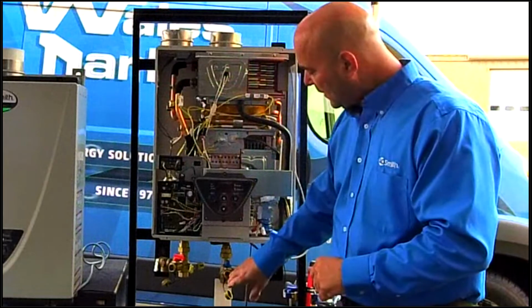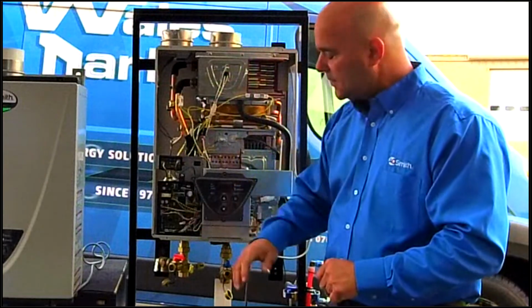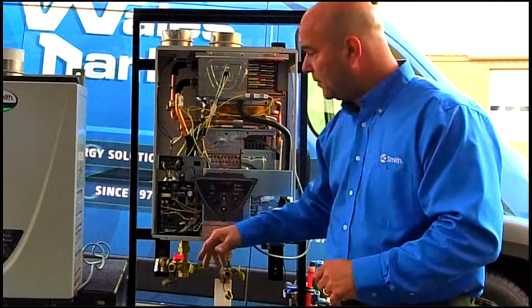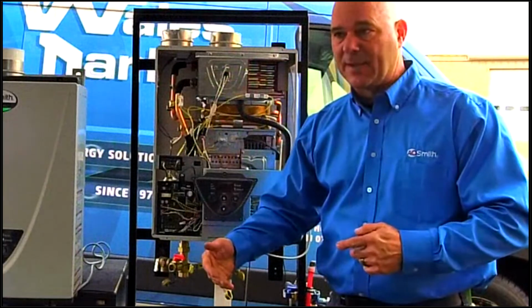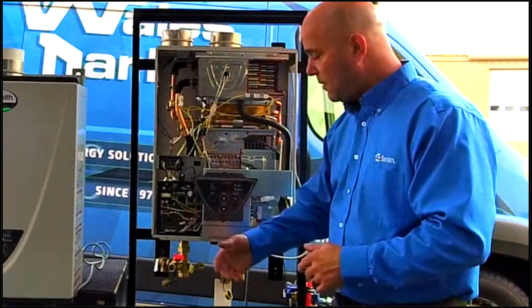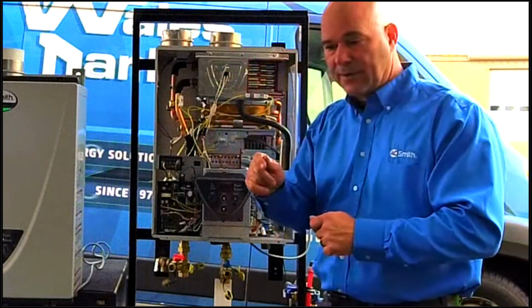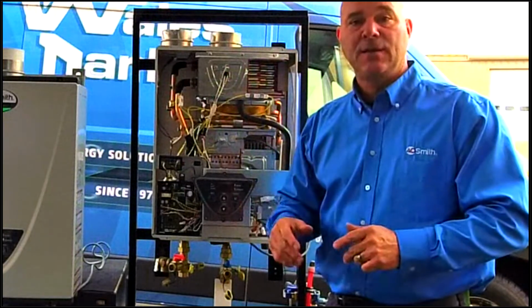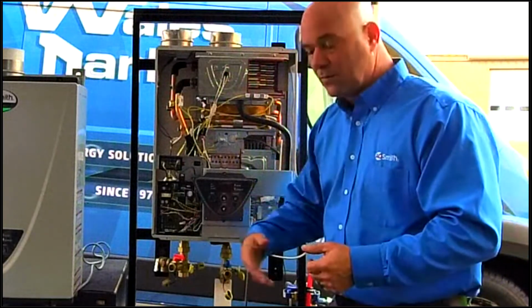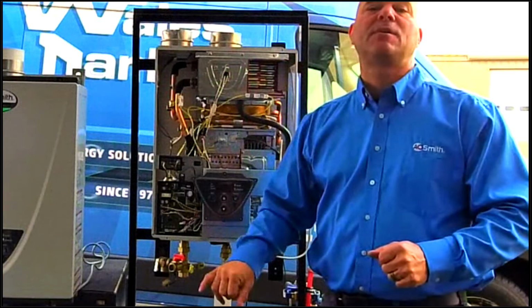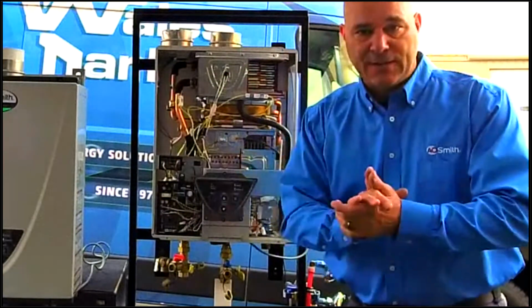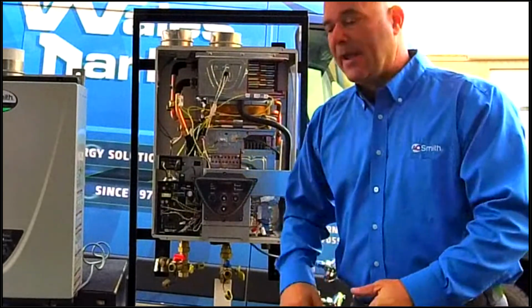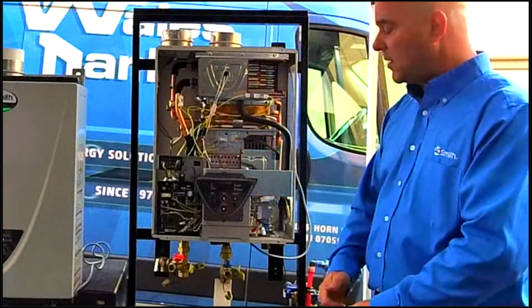So get your water flowing in, start to add your chemical, let it flow through. You may start to see some debris coming out, some different color water coming out. You'll see a greenish blue sometimes, depends on what's in the water. And you'll continue to add your chemical, and you'll run it like that for, let's say, 20 minutes. After you're done running it for 20 minutes, you shut your pump off.